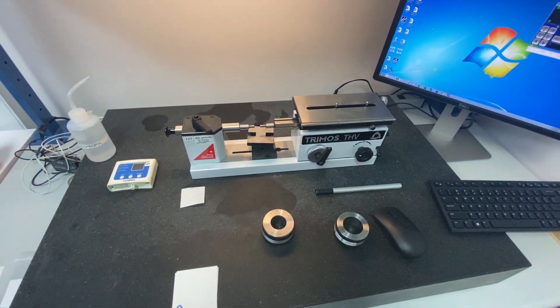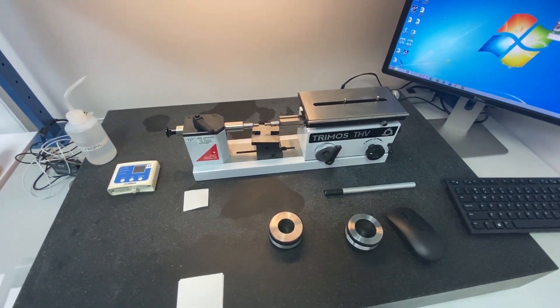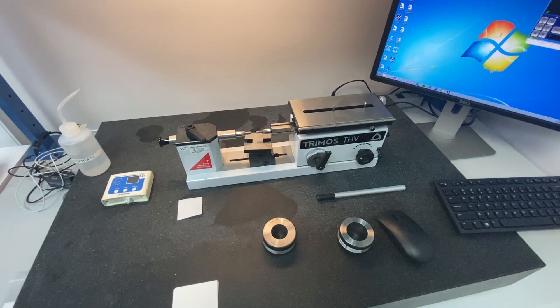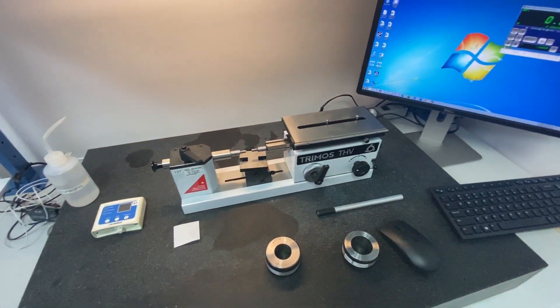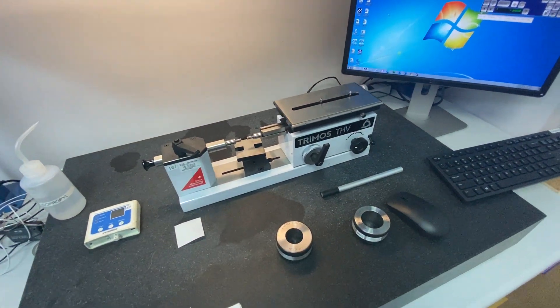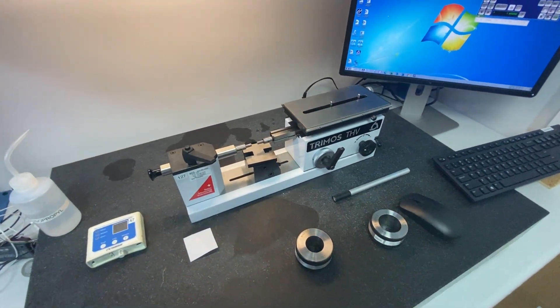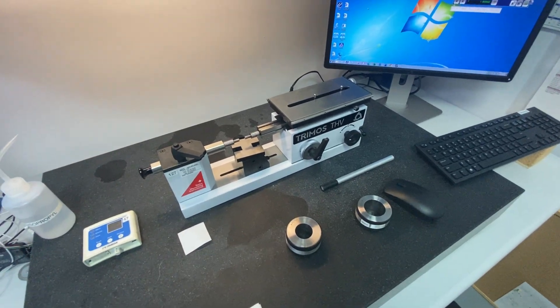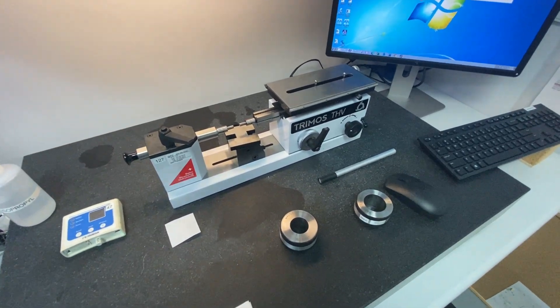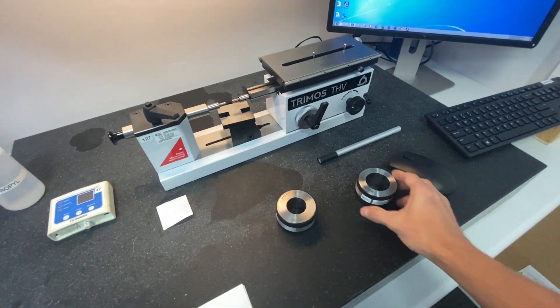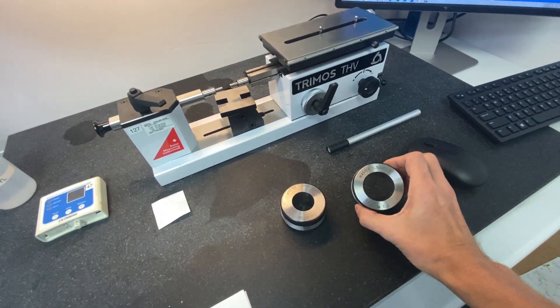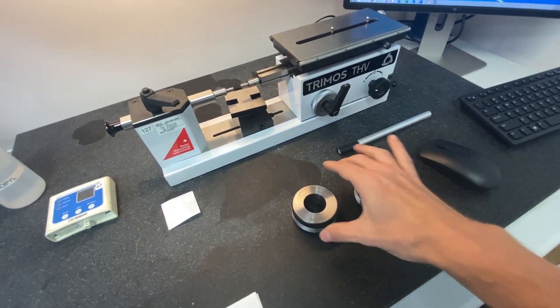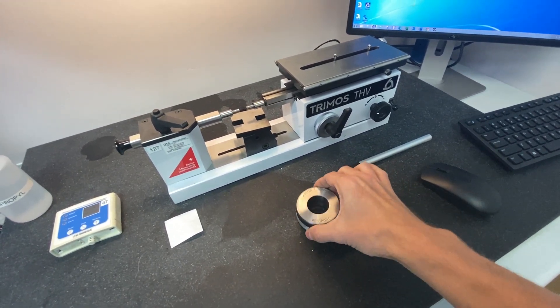In this video we will demonstrate how to calibrate a ring gauge. Typically you would match two ring gauges of the same size or as close as you can, but we don't have two of the same rings because we were showing off our rings, so we have a 1.5 inch ring and a 1.2.